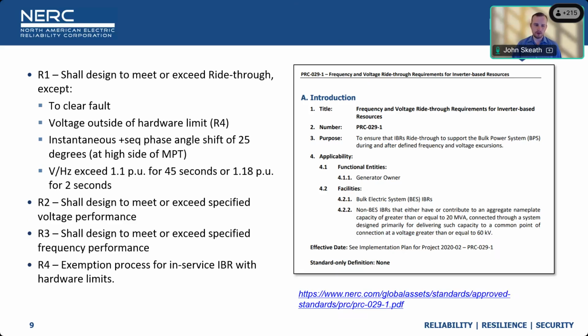But I'm going to go deep into these specific requirements to really show where the specific item is identified. So R1, I'm not citing the actual standard language, but giving a broad overview, is requiring the generator owner to design and meet or exceed the ride-through except in certain scenarios. And so we've identified already that the owner of an IBR shall meet or exceed ride-through under the normal operating state, except for these operating states, and that is to clear the fault, the voltage is outside of hardware limits, and that has ties to the R4 exemption process.